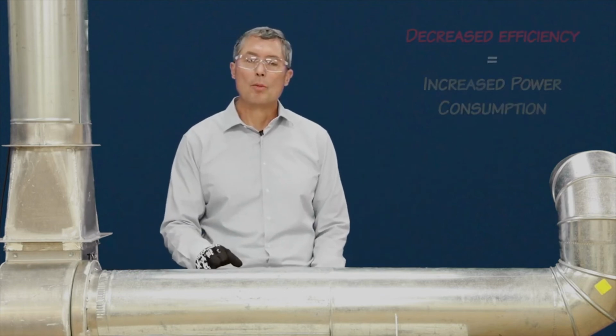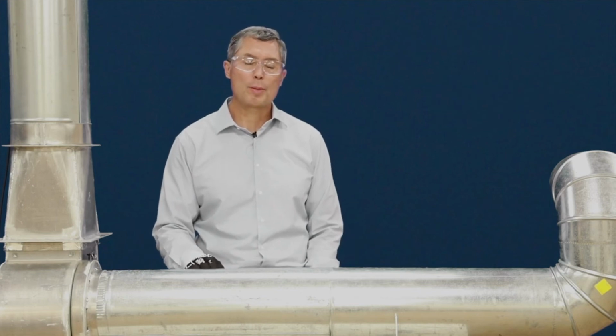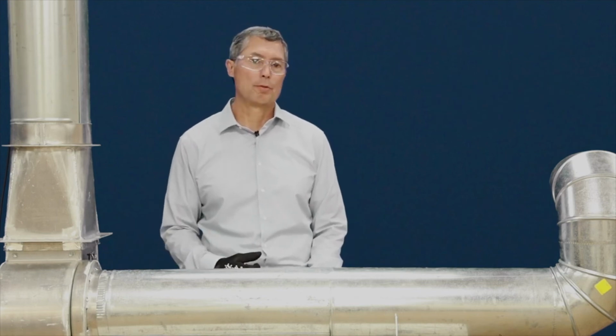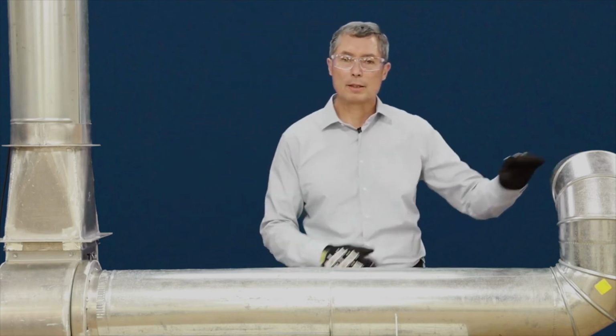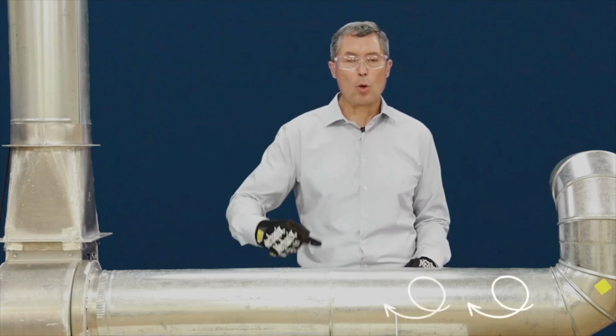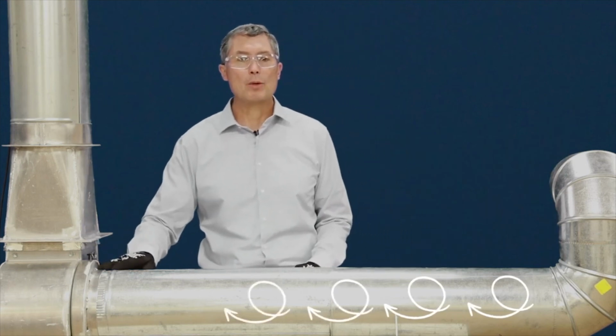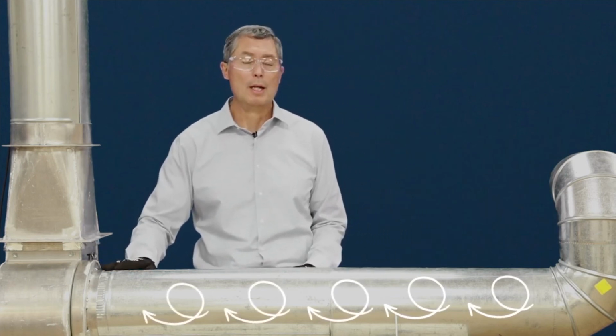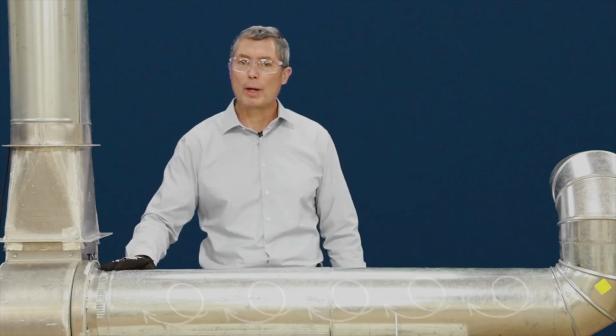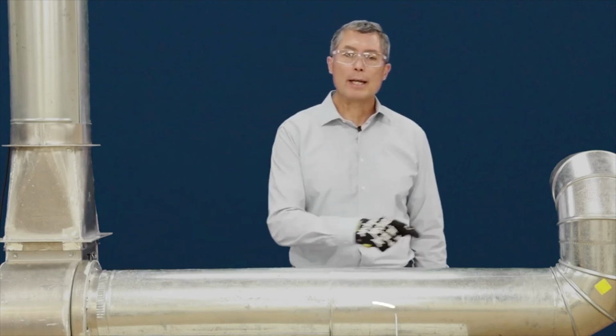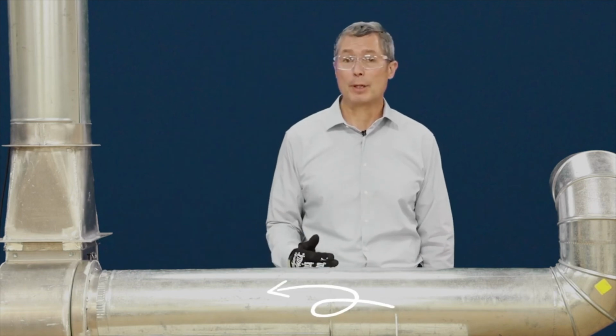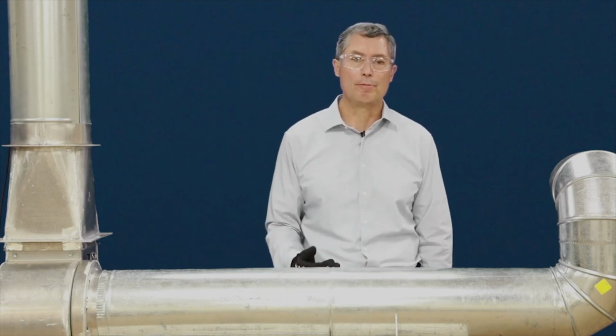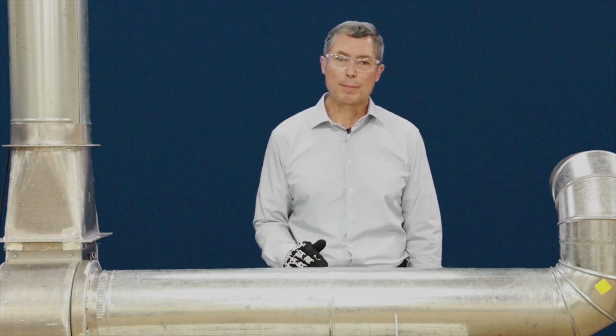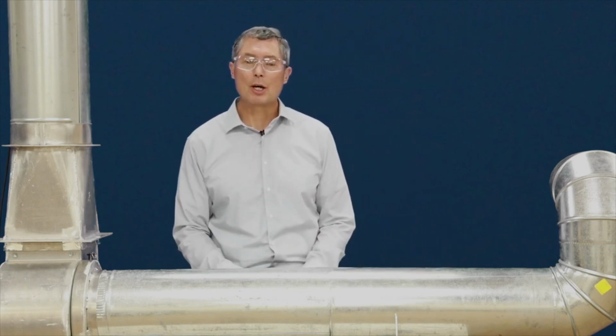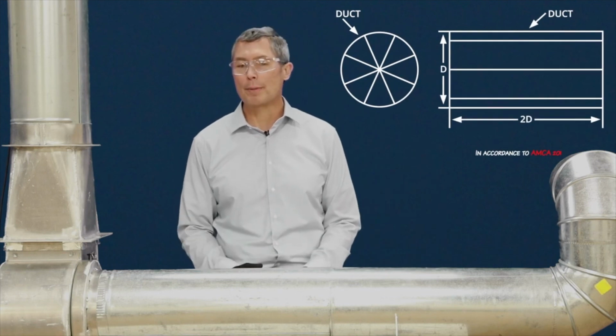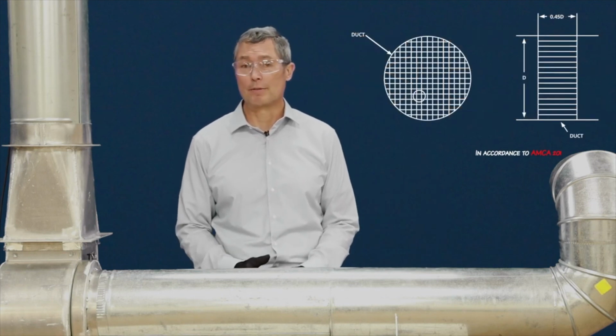Straight runs of ductwork, while they typically help with fan performance, don't really work very well on circular flow patterns. So if we create a vortex going through the duct, air's going in a circular pattern, we have to remember that the fan wheel is also creating a vortex as well. Not quite as strong as this one, but it is creating one. And as a result, it can carry vortexes through duct for very extended periods of time. I've seen them carry as long as 300 feet. The only way to break that up is to put some kind of straightening vanes or splitter vanes inside the duct to help break that vortex, or to use some kind of diffuser in the duct, and that's effective as well.